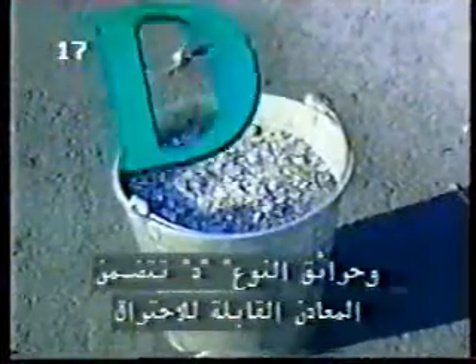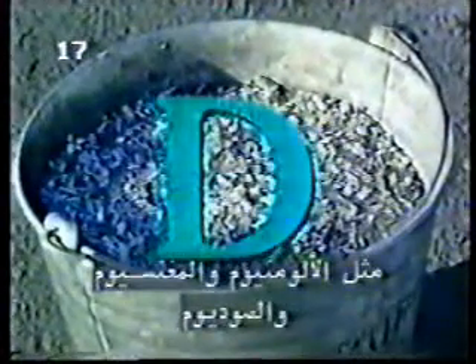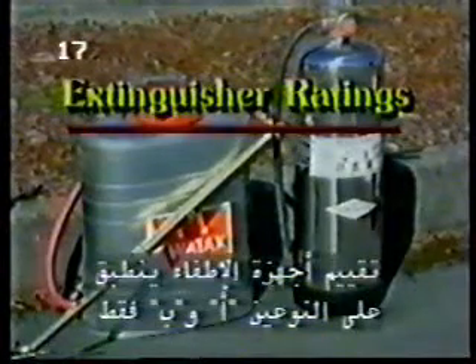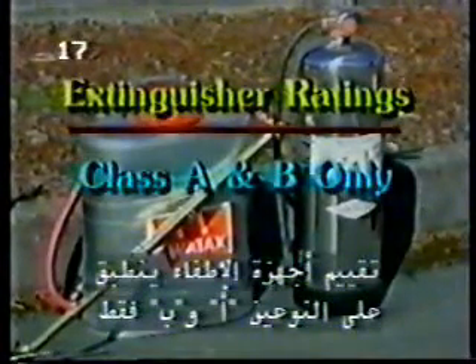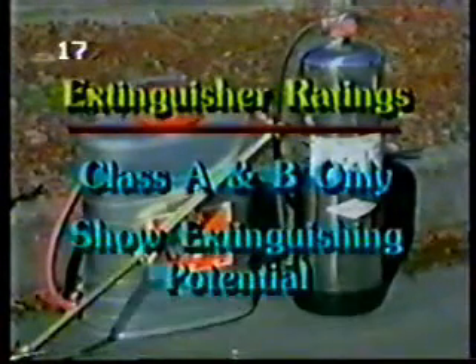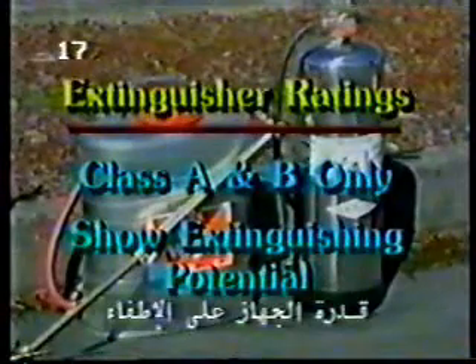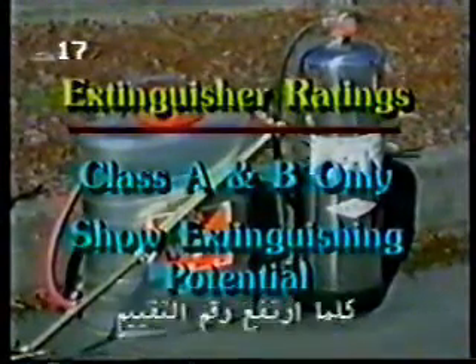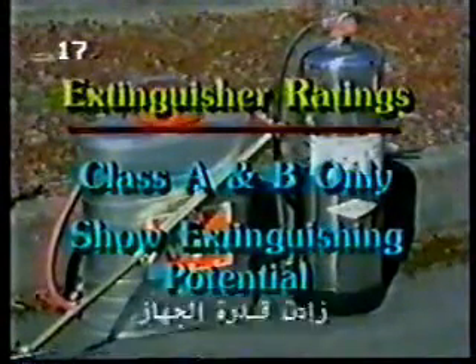Fire extinguisher ratings apply to Class A and B extinguishers only. The rating indicates the extinguishing potential of the extinguisher. The greater the number, the greater the extinguishing potential. For example, a 4A water extinguisher can extinguish twice as much fuel as a 2A water extinguisher, and a 5BC carbon dioxide extinguisher can extinguish 5 times as much as a 1BC.